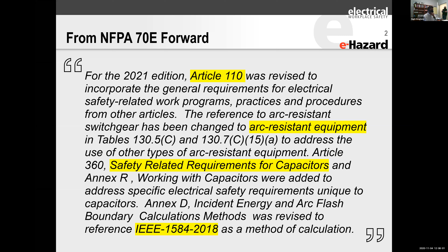Arc-resistant equipment does not mean equipment that is immune to an electrical arc flash. It means that if an arc flash occurs internally, that energy is constrained and redirected into a safer zone away from the worker. It does not mean the equipment will not fail and result in an arc. It just affects the influence of the arc on the worker.